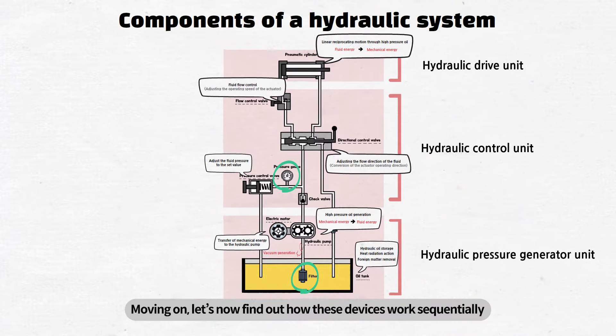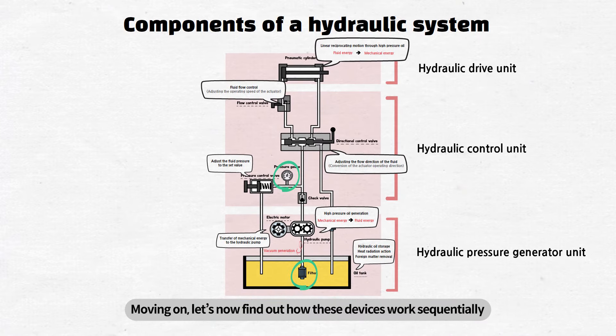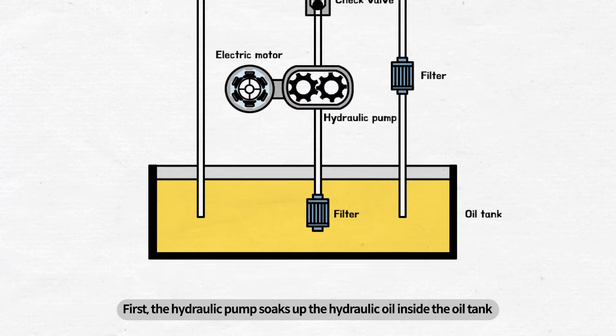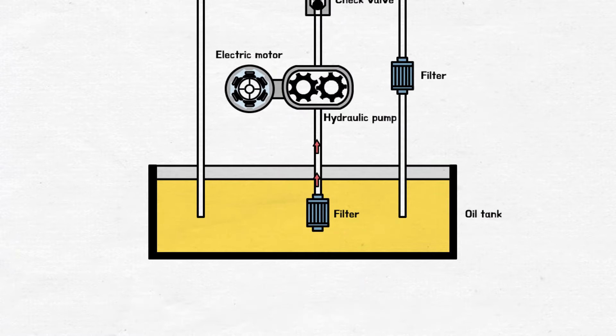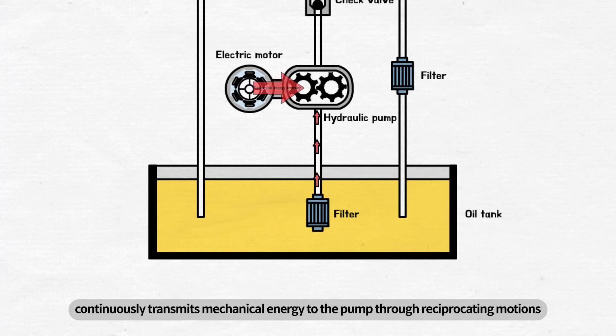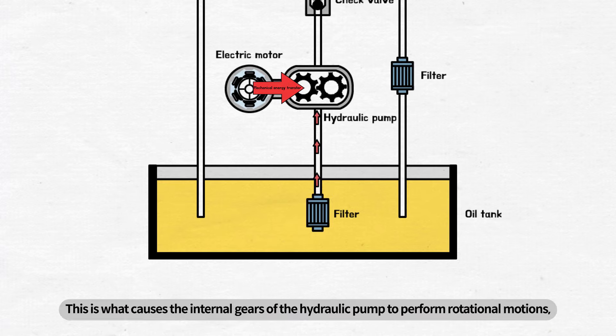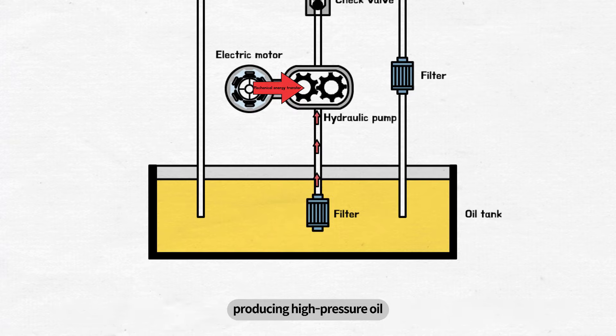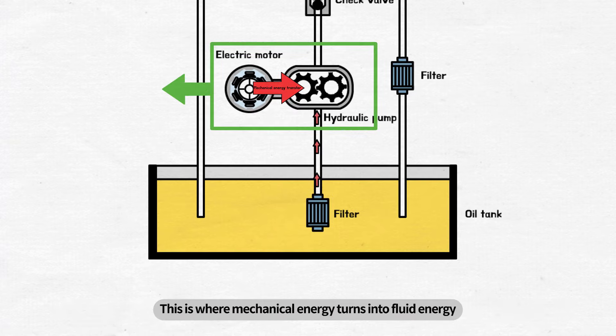Moving on, let's now find out how these devices work sequentially. First, the hydraulic pump soaks up the hydraulic oil inside the oil tank. At this point, an electric motor connected to the hydraulic pump continuously transmits mechanical energy to the pump through reciprocating motions. This causes the internal gears of the hydraulic pump to perform rotational motions, producing high-pressure oil. This is where mechanical energy turns into fluid energy.